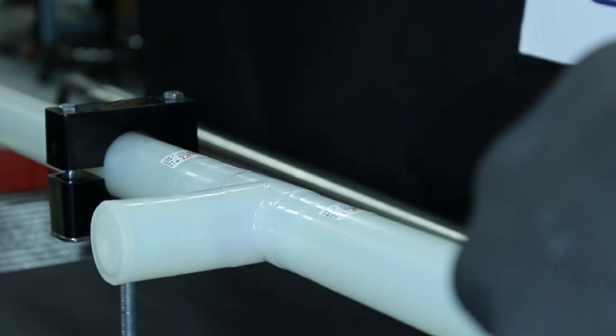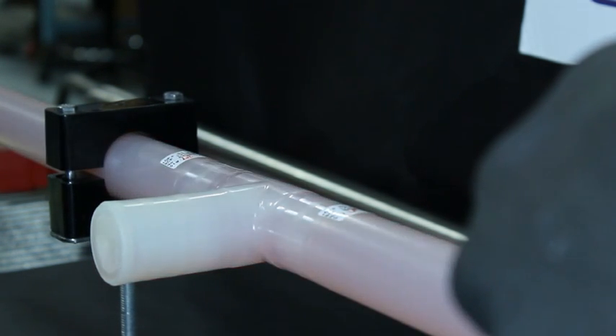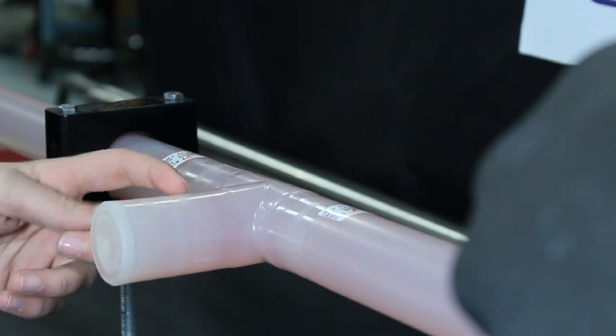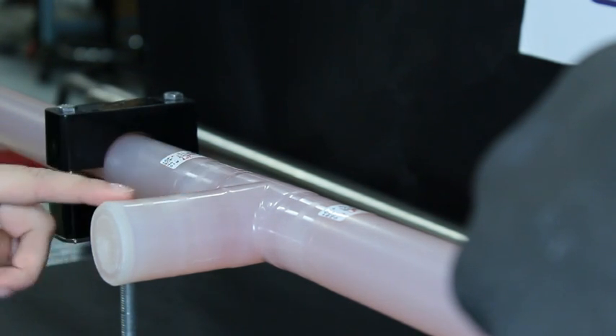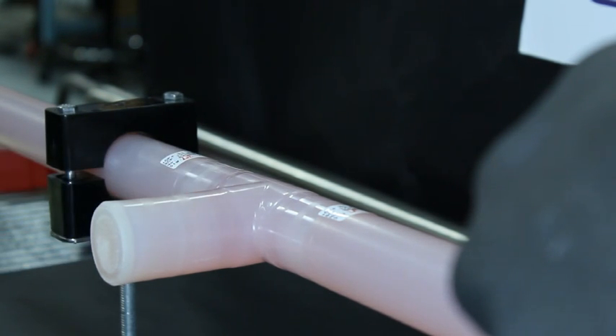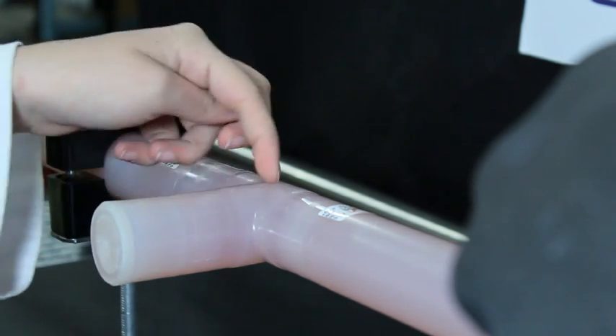Now with our T rotated to the 90 degree position, let's turn on our pump and see if we can get rid of the air pocket. So as you can see, at a velocity of approximately 5 feet per second, our air pocket is very small and is bouncing around in this leg. This eliminates the cleanability problem almost completely as our end cap is being cleaned, as is our leg.